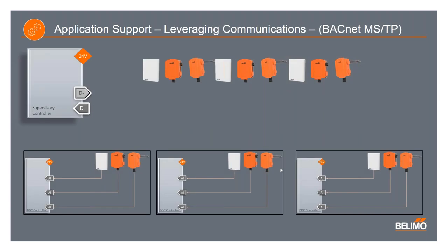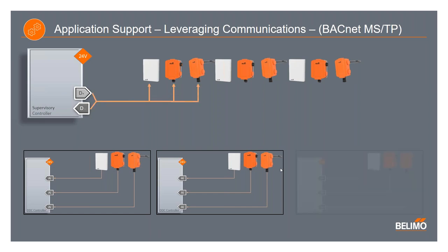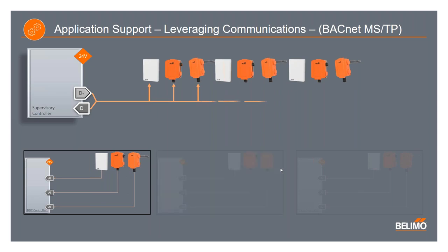Here we have a larger system — the same system represented on the previous slide but expanded across multiple zones. In this case, you have the same three sensors installed across three different zones. Rather than bringing the sensors back to the physical local controllers, the additional sensors can be added to the same MSTP subnet to reduce the physical inputs as well as reduce wiring and installation time, all while gaining the benefit of additional available objects on the BACnet sensor.